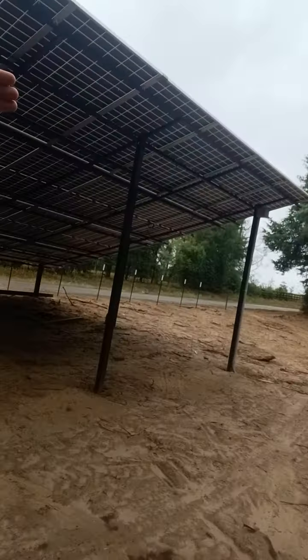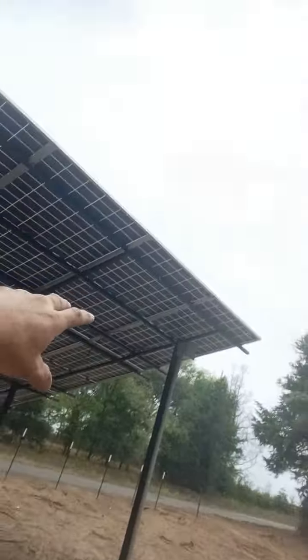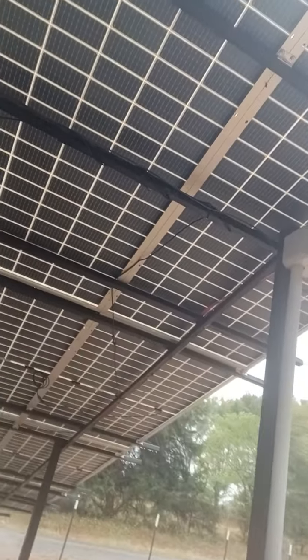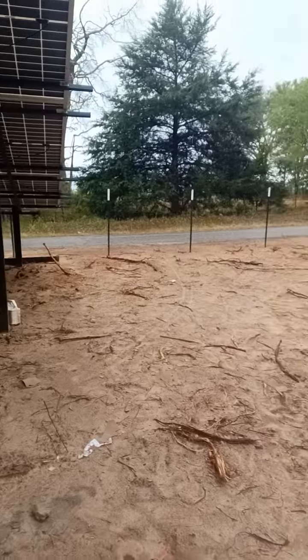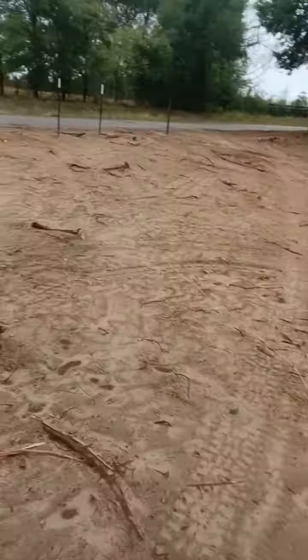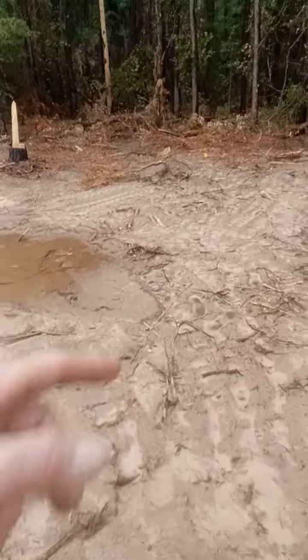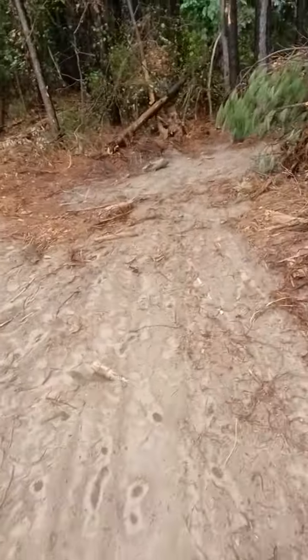We came in with three negatives, three blacks, plus a ground coming in from the top of this junction box — it's a 6x6x6 — coming into an inch-and-a-half conduit strapped to the body of the face. Everything's grounded, coming in through roughly about 240 feet. This is where I started getting real treacherous — I did not like this, not one bit.